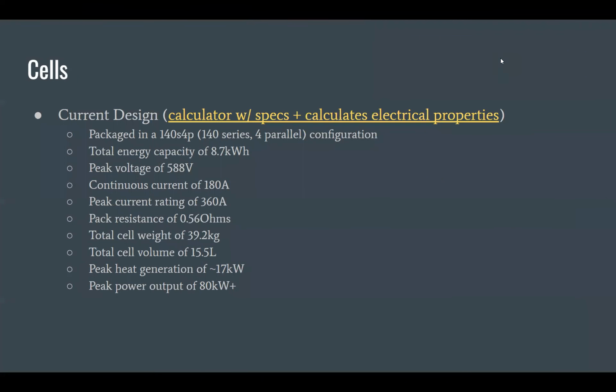Looking at our current battery design: our current design is a 140S4P configuration, meaning 140 battery cells in series, 4 in parallel. The 4.2 volts peak per cell adds up to our 588 volt maximum. The maximum of 45 amps per cell output with 4 in parallel gives us 180 amps output.